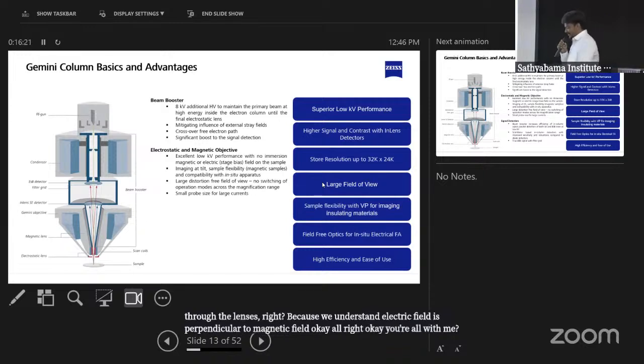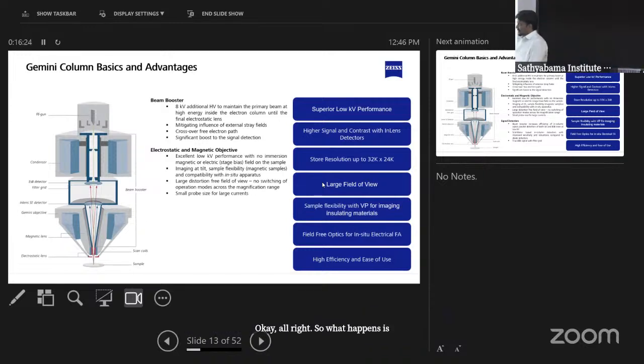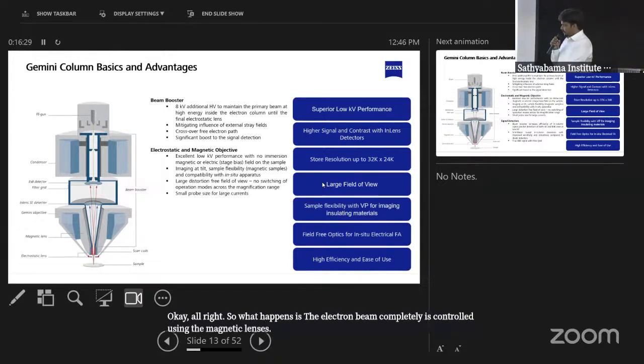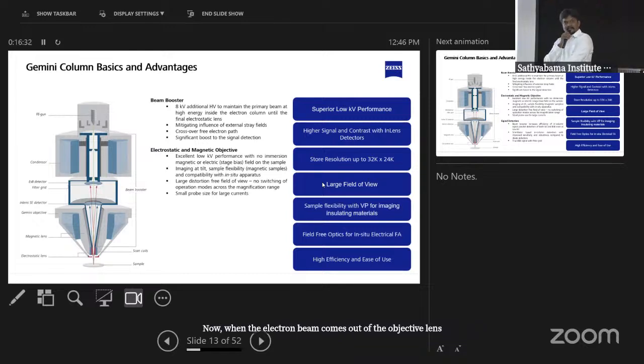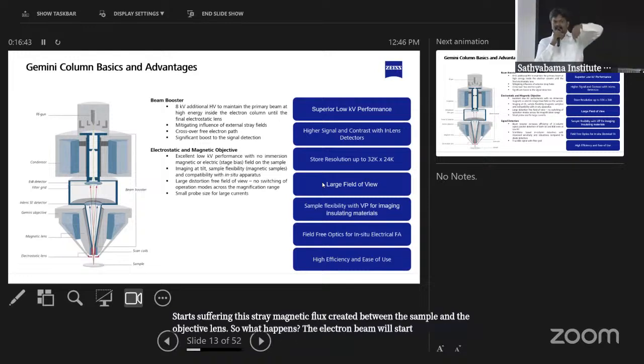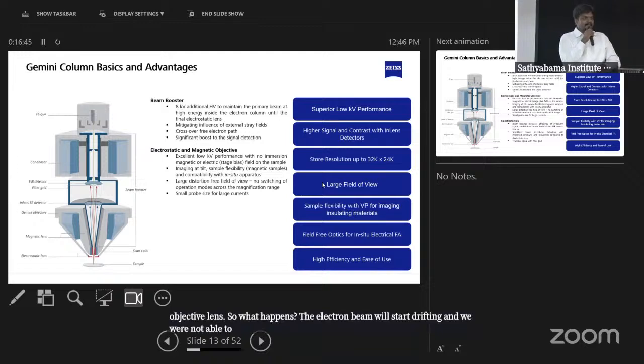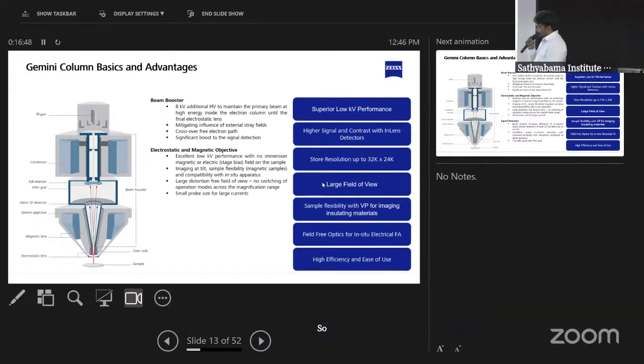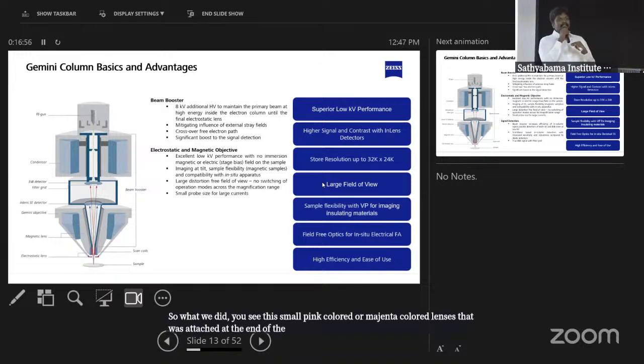Okay, all right. So the electron beam is completely controlled using the magnetic lenses. Now, when the electron beam comes out of the objective lens to interact with the sample, it starts suffering this stray magnetic flux created between the sample and the objective lens. So the electron beam starts drifting, and we were not able to do any characterization of magnetic materials at all. So what we did, you see the small pink or magenta colored lenses attached at the end of the objective lens, which are electrostatic. They are not electromagnetic, they are electrostatic.